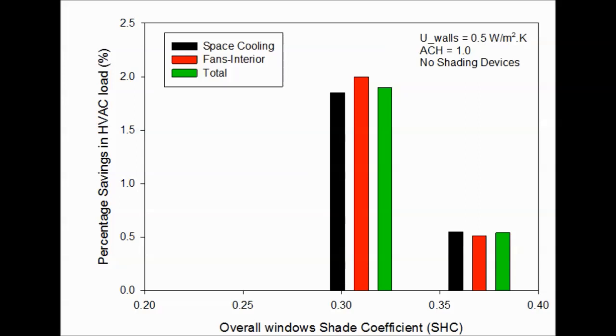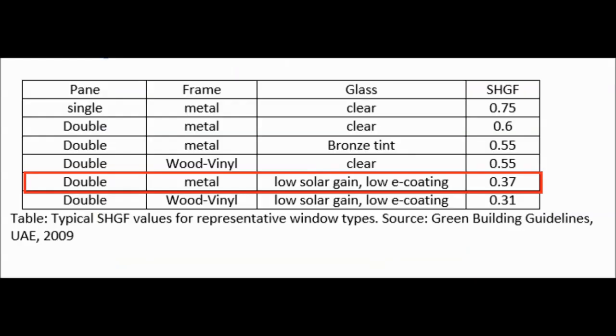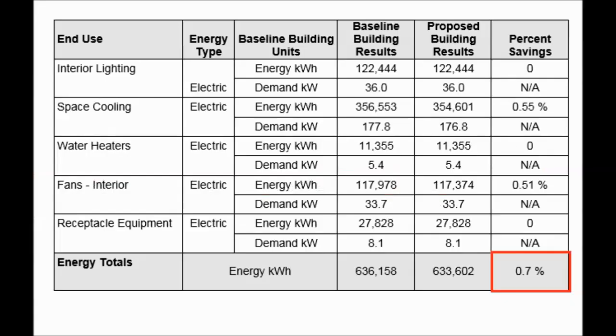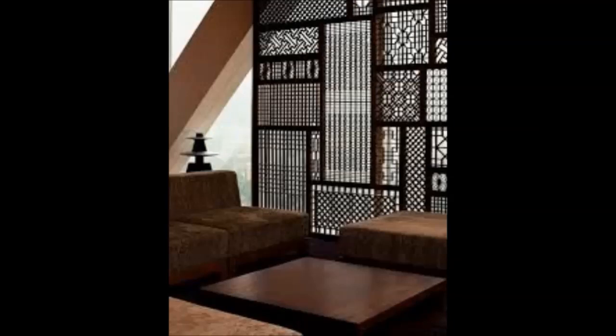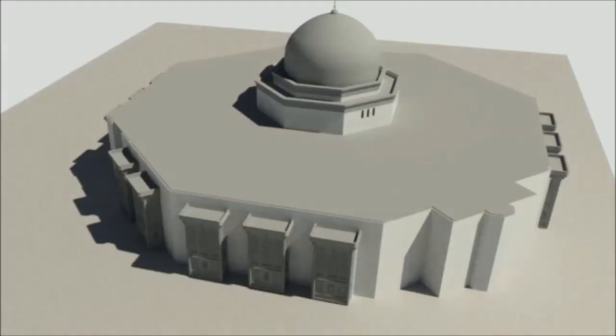Hence, there isn't much improvement in this area, except using the actual shading coefficient of this kind of windows, with a value of 0.37. The energy savings utilizing this new value of shading coefficient is almost 0.7%. The window shading used in this work is the Arabic lattice type, which is used to shade the whole window and allow sunlight to enter based on the perforation ratio of the lattice. This type of shading can be quite efficient in reducing the cooling load of the building, as well as adding a nice decoration to the outside of the building. Not to mention the effects of light and shadow that influence the inside lighting of the mosque.